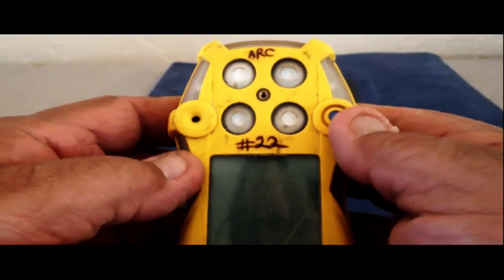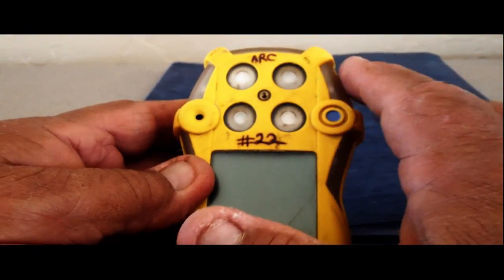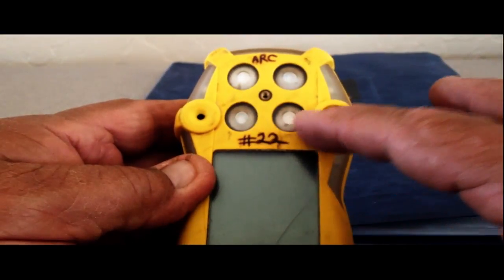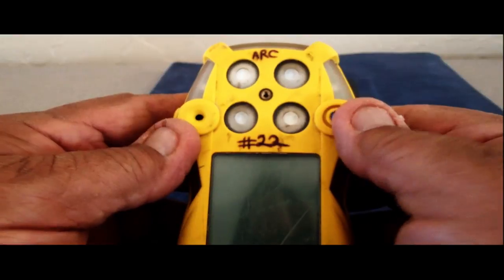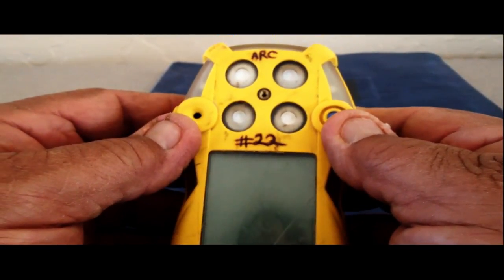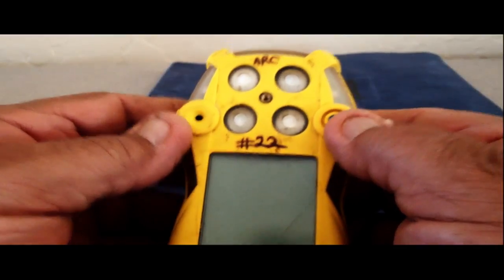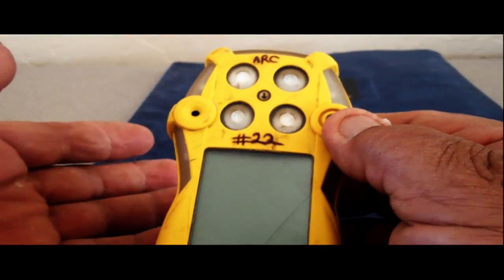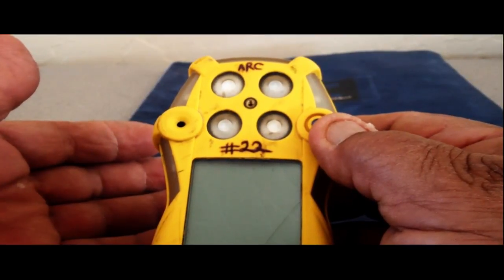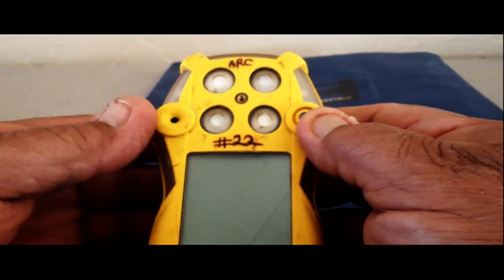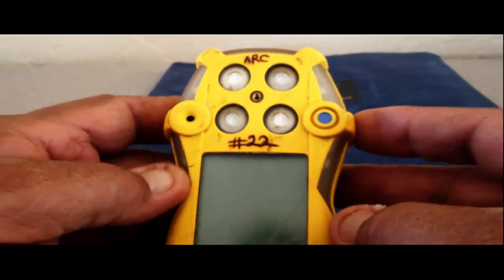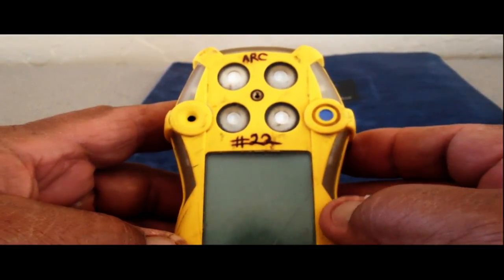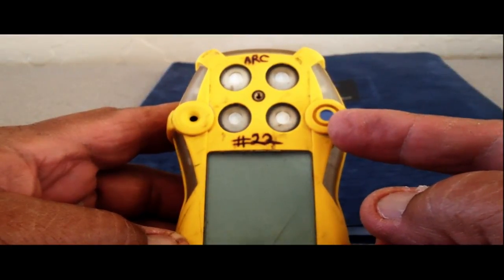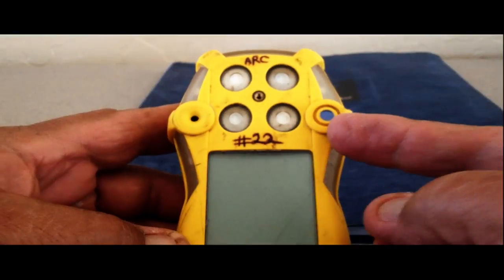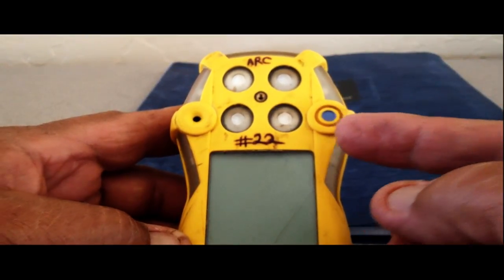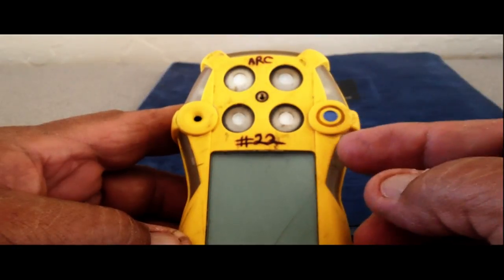So this is a diffusion type meter. So it only senses the gas that passes over these 4 sensors on the front, on the face of the meter. You can use this meter to detect gas remotely, but you have to lower the meter itself into the space and see what it gives you. And you use the peak function on this for that process. This is a single button operation meter. So you have this gray button. Use that button to turn it on, turn it off, check peaks, and put it into the calibration mode. We're going to do all of that here.